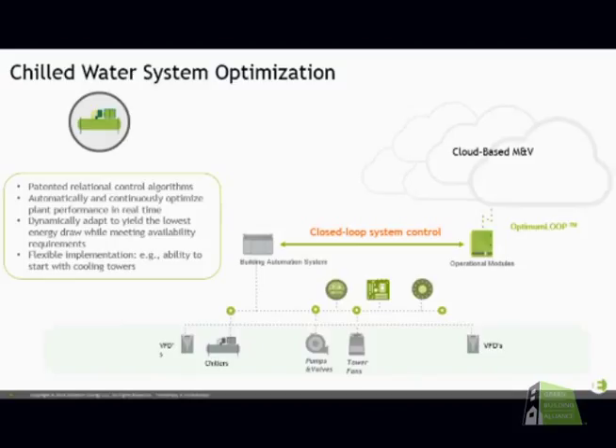And there's a variety of different manufacturers for all of those. But from the building automation system, that BAS is taking information back through all those sensors and controlling the plant. So whatever the chill water set points are, all the details for the plant. So again, what I was talking about before, having condenser water set point coming from the cooling towers, that information is typically fed through the building automation system to the cooling towers, and that's what varies the VFDs today.